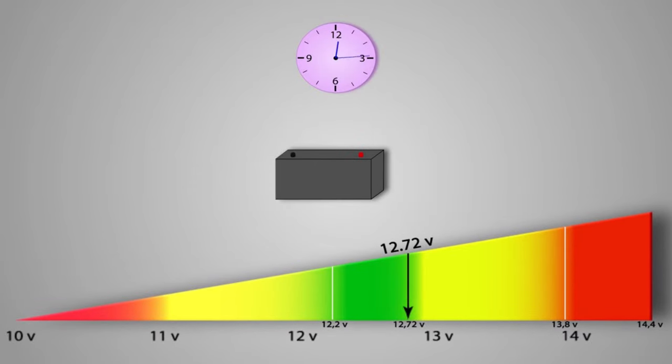Float voltage is measured while idle and without use for a few minutes. The minimum value is 12.2 volts and the maximum is 12.7 volts.